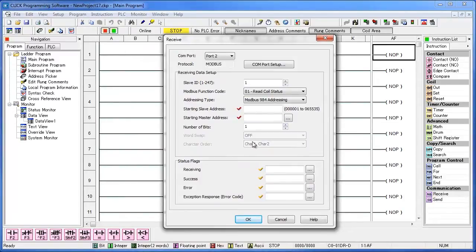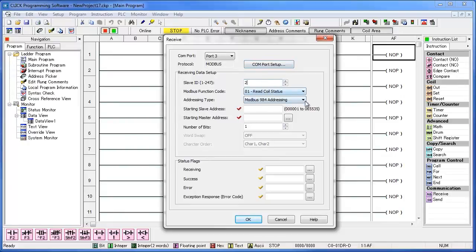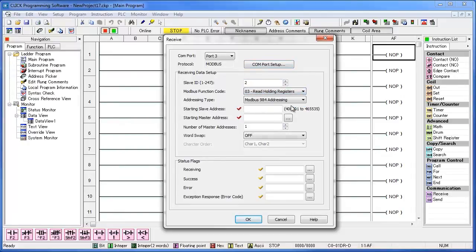We need to change the COM port to port 3. Change the slave ID to whatever you set the network address to in the SOLO. In my case, I need to set that to a 2. Make sure the Modbus function code is set to 3, read holding registers. You can leave the addressing type alone for now.